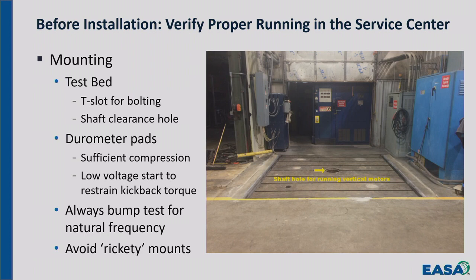Okay. There's other ways of test running solid shaft motors with the shaft out the bottom. I've seen people set it up on blocks of wood. That's not necessarily bad. It's got some potential problems. Durometer pads work pretty good. If you're not familiar with durometer pads, they're a soft pad which compresses from the weight of the machine and isolates it so that it is basically floating. If you set the vertical motor up on blocks of wood or on durometer pads, it's a good idea to start that machine on reduced voltage. If you start it on full voltage, the torque can cause the stator to spin and give you some problems that you don't want to encounter.